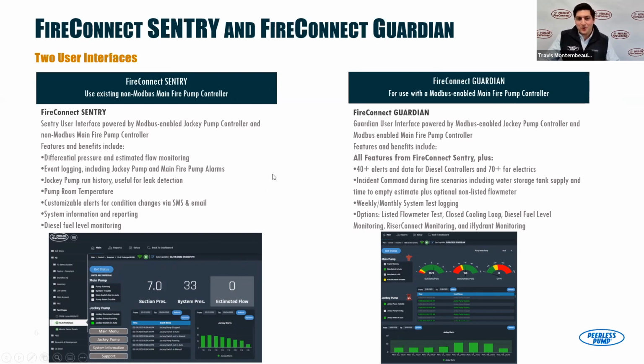And we connect to those 4 code mandated dry contacts from your main fire pump controller. So in this case, this is a diesel system. So pump running, system trouble, main switch not in auto, and pump room trouble. So we take those dry contacts and we can still send alerts and signals and start to do things like monitoring tests from that.